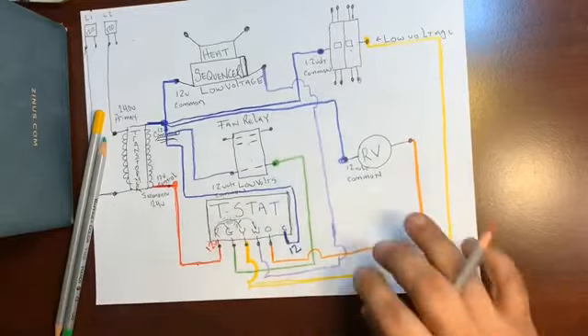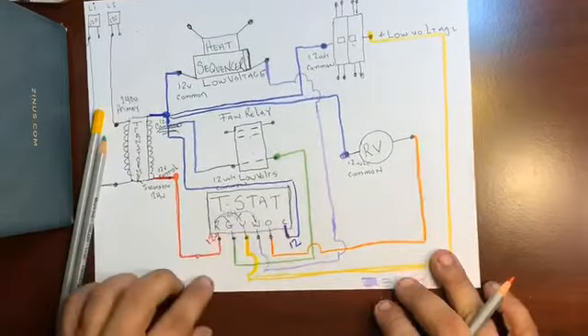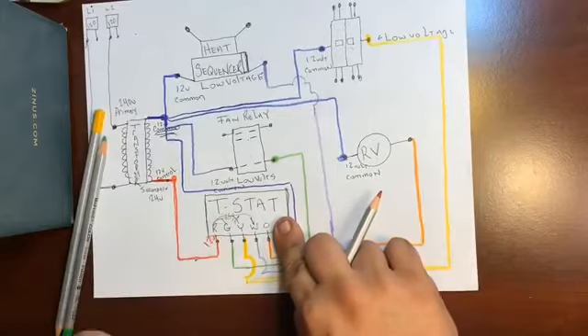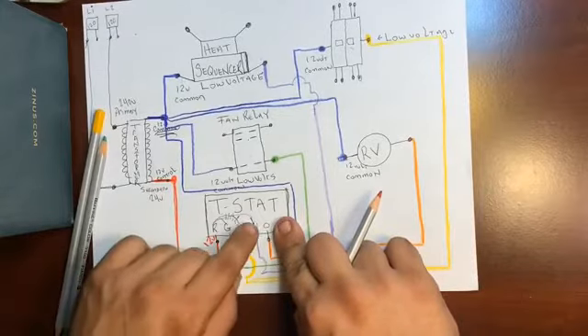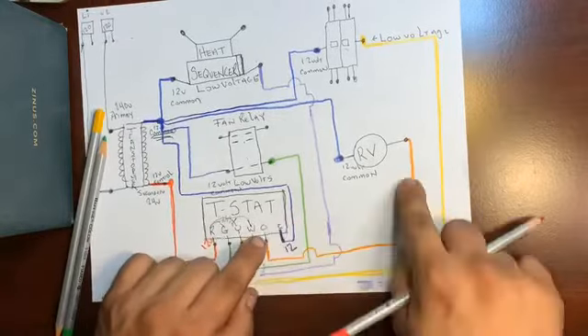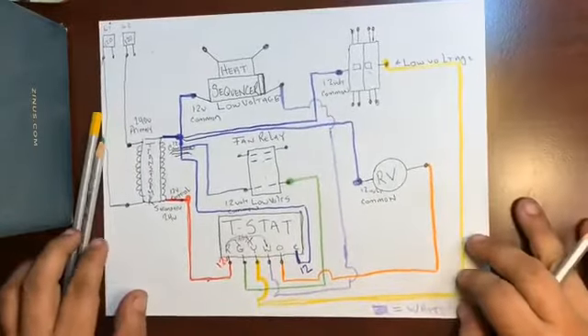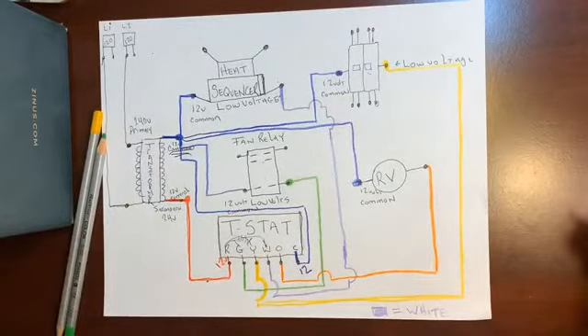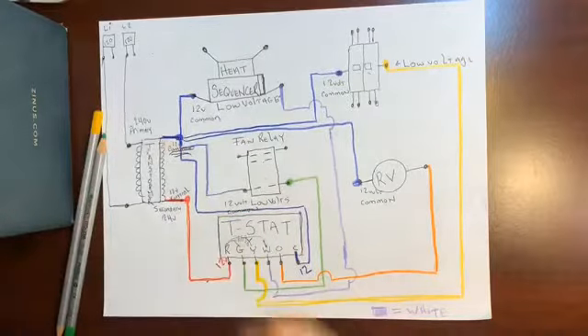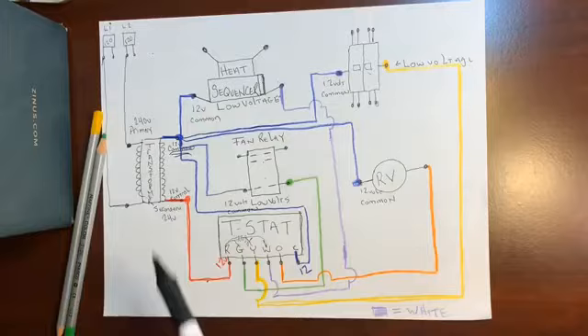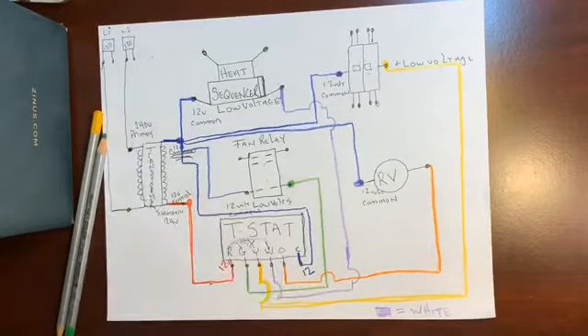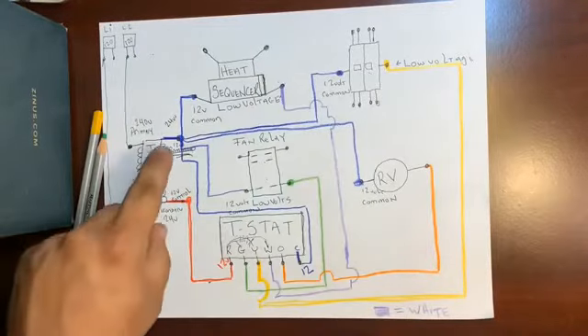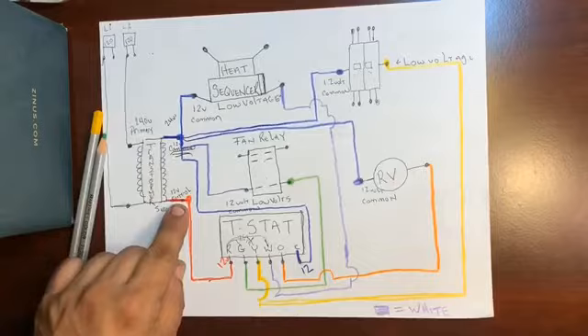But just keep in mind, this red will never jump to the common. It would only jump to the green for the fan, yellow for the compressor contactor, white for the heat strips, or orange for the reversing valve. This is our low voltage diagram. As we can see, everything starts with L1 120 volts, L2 120 volts, feeding the primary side of the transformer, 240. Mr. Transformer says, thank you, you've given me my 240, now I'm gonna give you your 24 volts. I'm gonna give you 12 volts on the common side, and I'll give you 12 volts on the control.